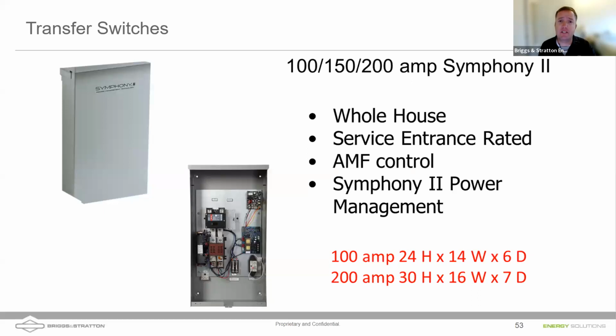This is the Symphony 2 here, where the generator is looking for grid, and this transfer switch is not only looking for grid, but also generator voltage, which will then, only if it sees the loss of utility and generator proof the voltage, transfer.